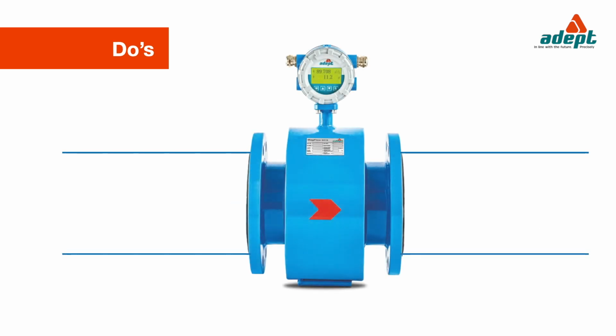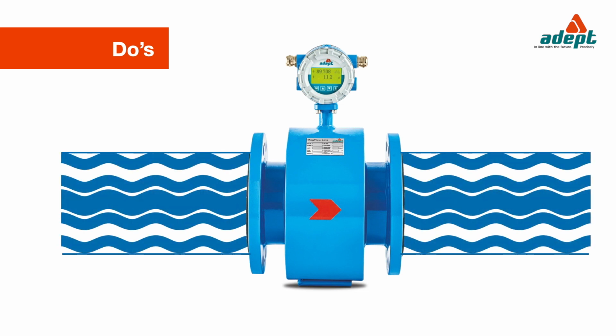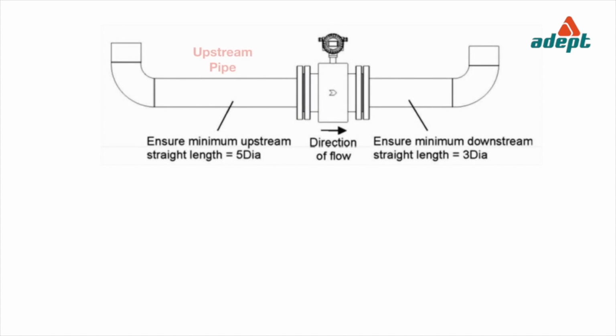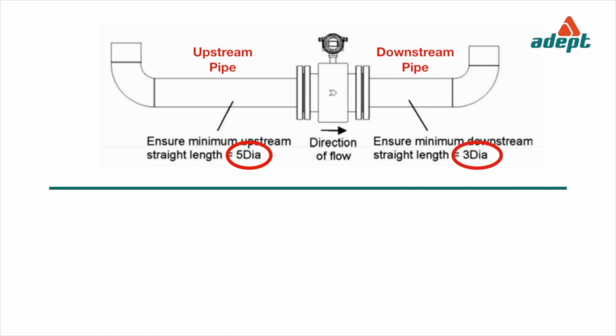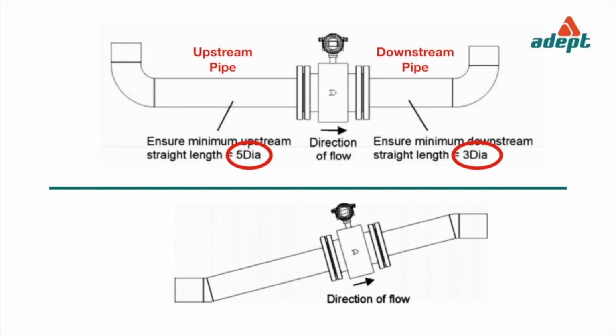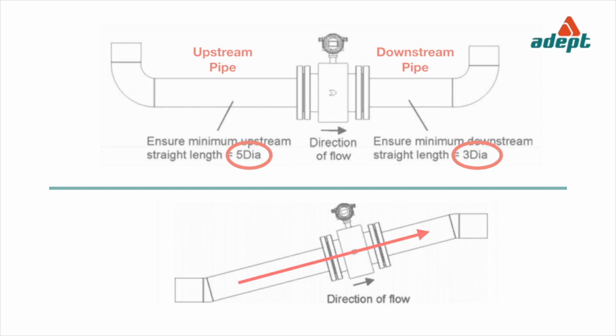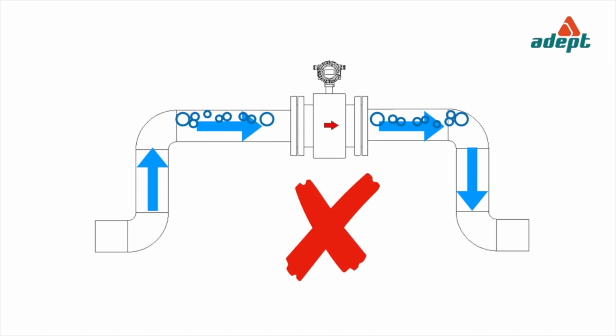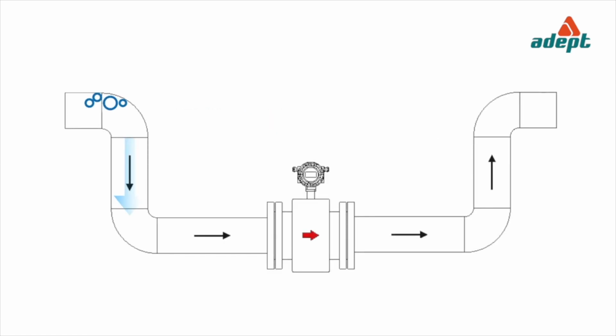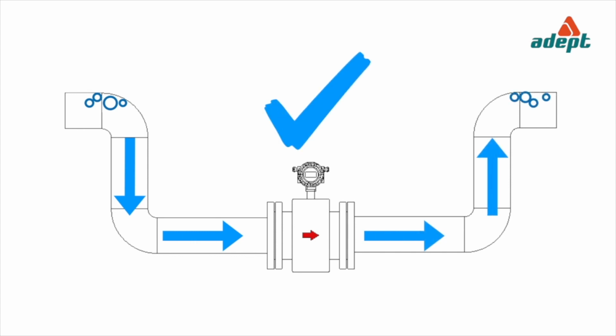Do's. The flow tube must be full of liquid to avoid erratic measurement results. Ensure straight pipe lengths on either end of the flow tube, 5 times pipe diameter length of piping upstream and 3 times pipe diameter downstream from the center of the flow tube. The flow tube may be installed in horizontal pipelines, preferably with a slight upward gradient in the direction of flow. The piping layout must prevent any buildup of air. Any entrained air should be carried out of the flow tube by the liquid flow.